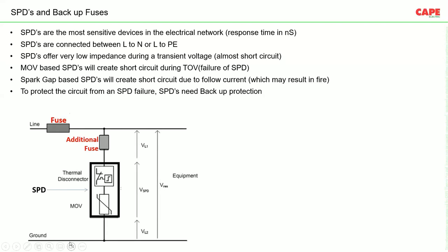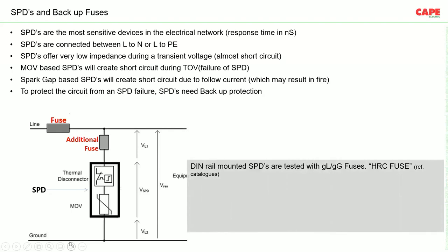Once the SPD reaches end of life, we must ensure it disconnects from the circuit. For this purpose, we use an additional fuse called backup protection. Generally, DIN-rail mounted SPDs are tested with gL/gG fuses or HRC fuses. All standards recommend gL/gG and HRC fuses only for SPDs. This backup fuse is only required when the line fuse exceeds a specified value.